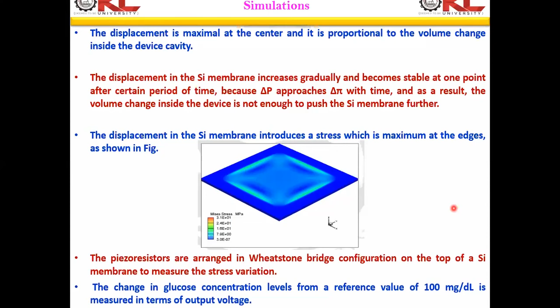For the change in glucose concentration levels, with the reference value of 100 mg/dL, we have done the measurement in terms of output voltage. The change in glucose levels outside the device is measured with respect to the reference solution, that is 100 mg/dL, with many dimension variations and optimizations of length, width, thickness, and so on. The output voltage varies with respect to the pressure for different dimensions of the silicon membrane. We observed that the output voltage across the bridge increases from 0 to approximately 21 millivolts after 40 minutes for a device where the silicon membrane dimensions are 3, 3, and 10 micrometer thickness.